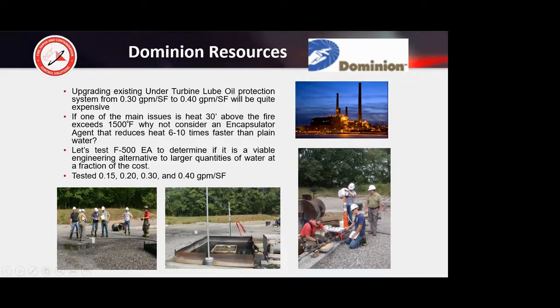This gentleman over here, showing you how old I am, Mark Boone. And at one time, Mark Boone was the chairperson of the NFPA 850 Technical Committee. So they set up a series of tests to see what the F500 would do. They said, let's test to see if this is actually a viable alternative to the larger quantities of water. So they tested 0.15, 0.2, 0.3, and 0.4 gallons per minute per square foot.